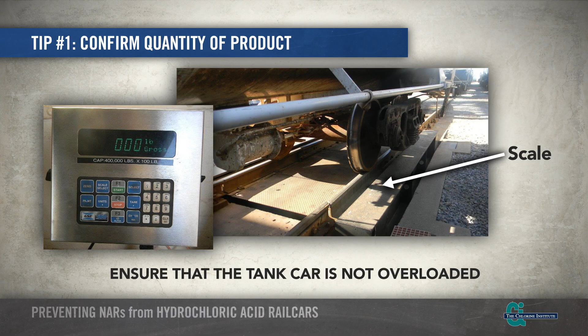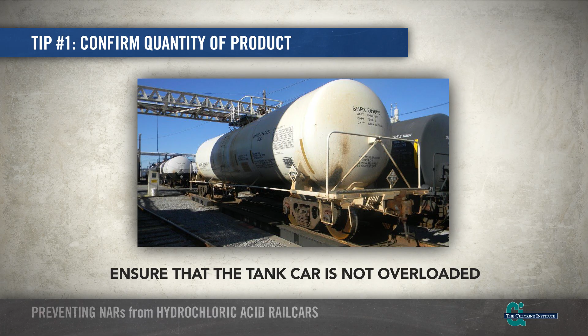The first thing you should do before closing up a loaded car is to confirm the quantity of the product that has been loaded. This can be done by verifying the weight indicated on the scale and by visual inspection through the fill hole in conjunction with gauging the tank car using strapping charts or outage tables. Verifying the quantity will ensure that the car has not been overloaded during the loading process. This will help reduce the chances of an NAR during shipment.